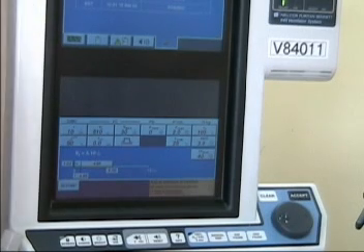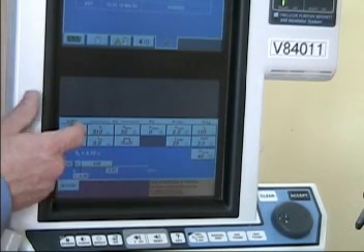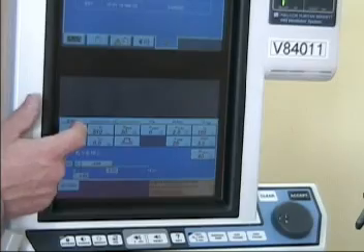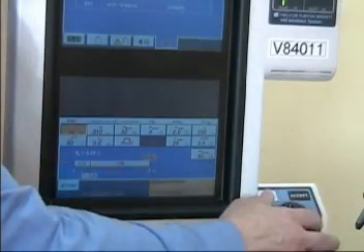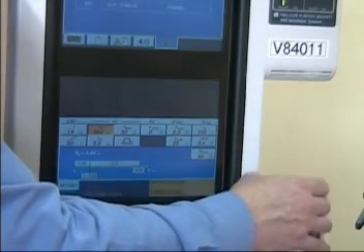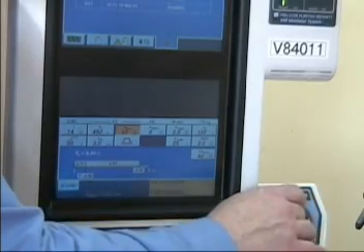Note the patient is not being ventilated. The machine is still in standby mode and is not connected to the patient at all. So we can go in and check our order, determine what we want to give the patient. Set the SIMV rate — we'll set it at 14. The volume we want is 450.